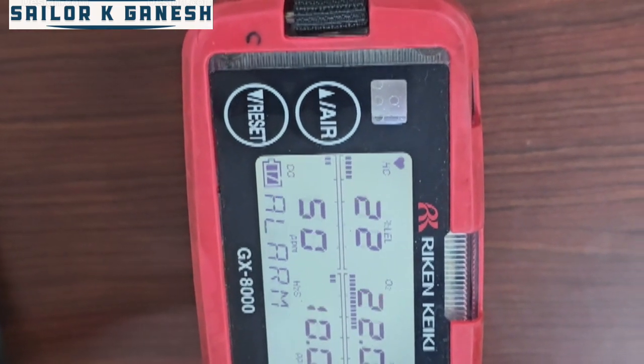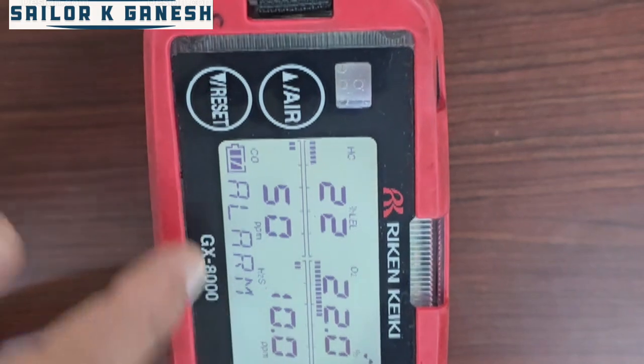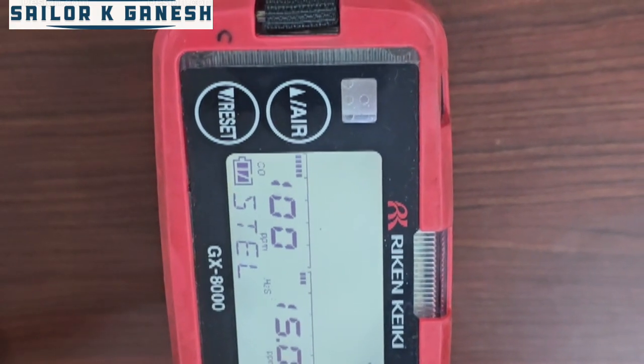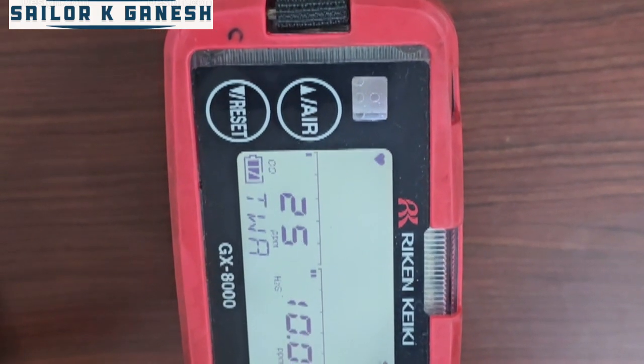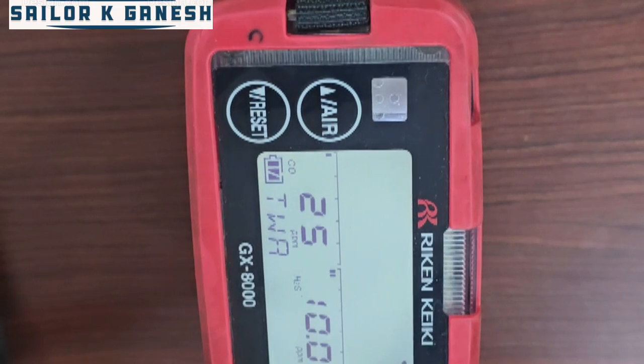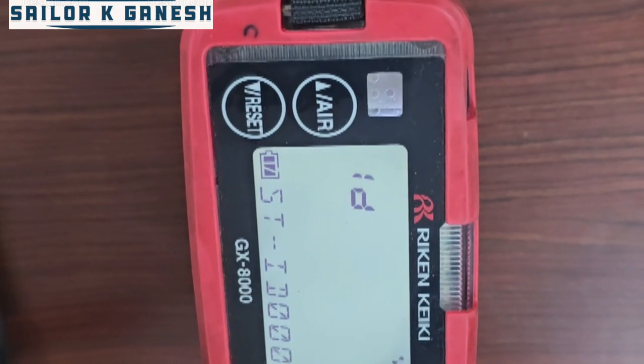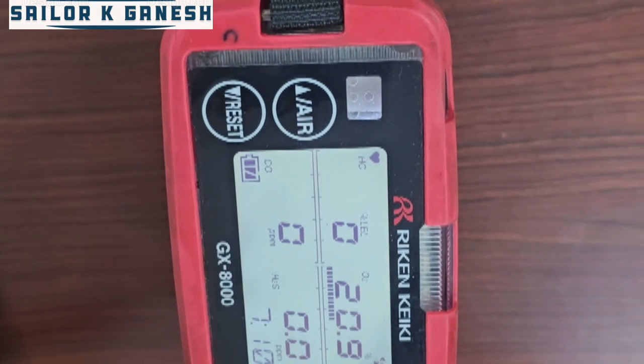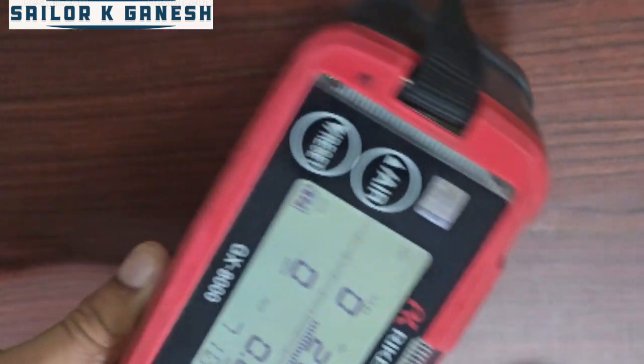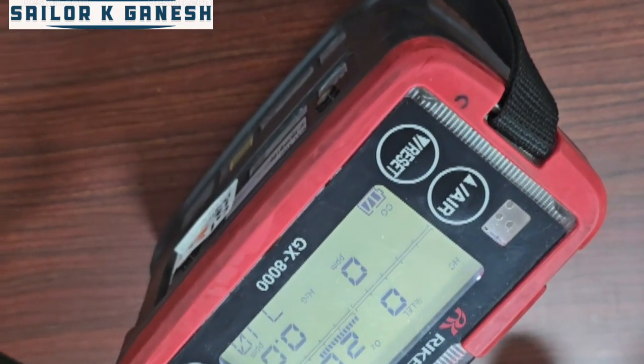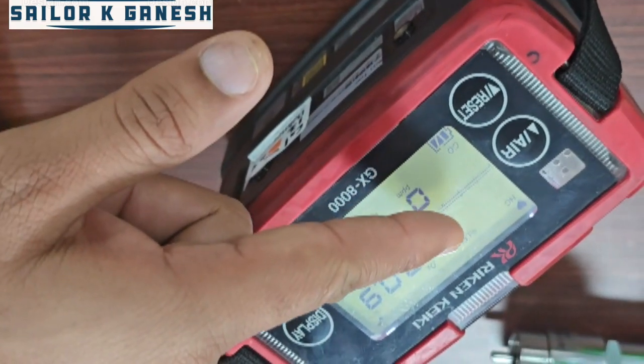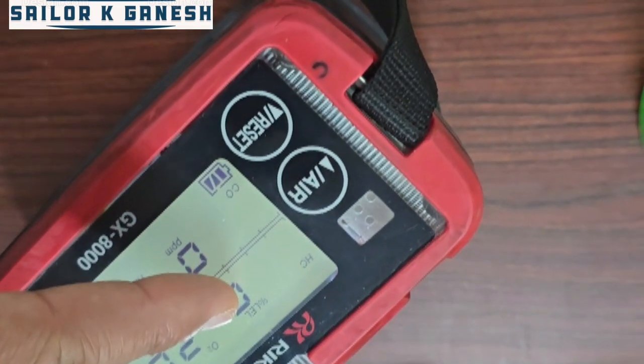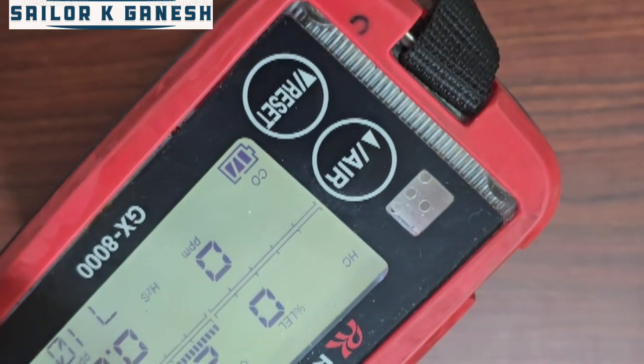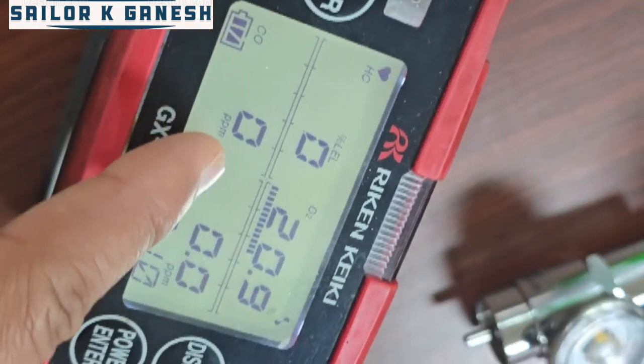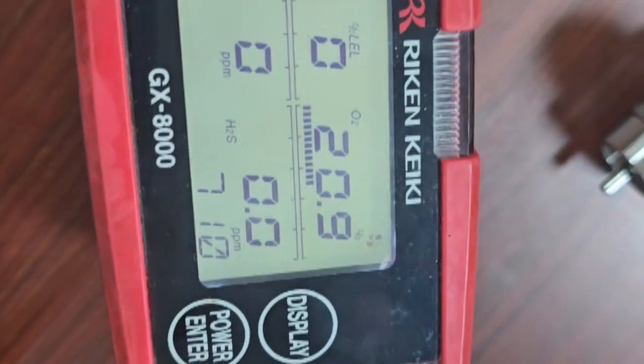These are the alarm settings and warning settings. This alarm setting is already set inside. You can change this alarm setting by going to the calibration mode. And now this equipment is ready to use for any tank atmosphere. Now as you can see, hydrocarbon is 0% LEL, oxygen 20.9, CO, carbon monoxide, is 0 and H2S is 0. So this is the idle condition of this equipment.